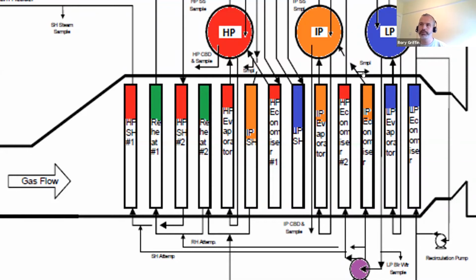The remaining flow goes up to the IP drum and repeats the process into the evaporator. You separate your steam and water, join the top of the drum, from the top of the drum to the superheater section, and then out to the, well, not quite the steam turbine yet, but we'll come to that in a sec.